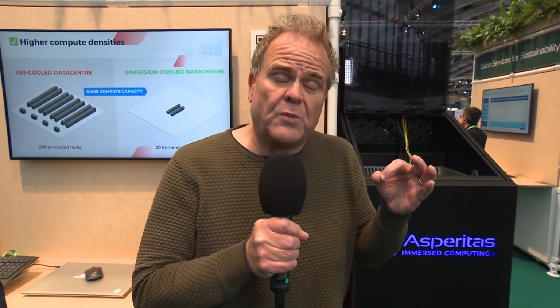Heat we have to get out of the data center. And to get heat out of the data centers, a lot of the power they're using - in fact the majority of the data center's power usage - is often used to cool the data center. That's because air is a very poor heat transfer fluid. It's much better if we can get the heat into fluid right away. If we do that, we don't have to use as much power. In fact, we can use very little power to get that heat out of the data center if we move the heat directly into fluid. That becomes also more important.